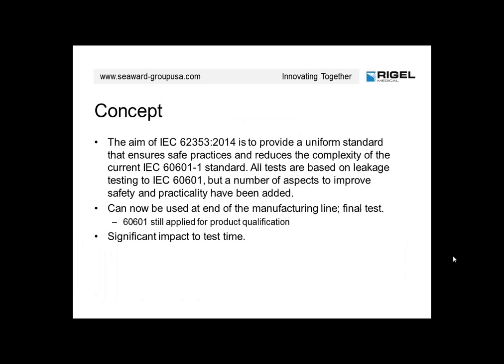So the concept was to come up with a uniform standard for safety testing. One of the things about 60601 is that it really didn't go into any detail on how to do field-based equipment testing. 62353 does that for us. The tests are based on the 60601 standard, but with a couple of changes to add safety and practicality to the testing.